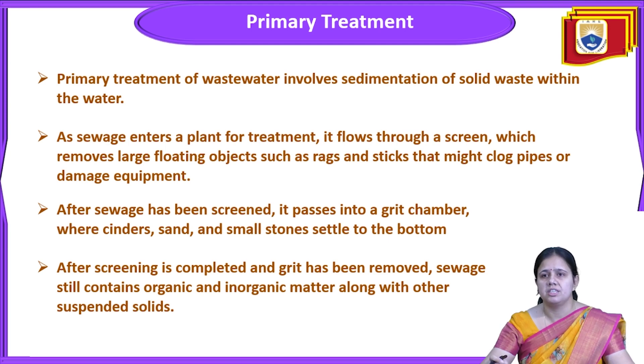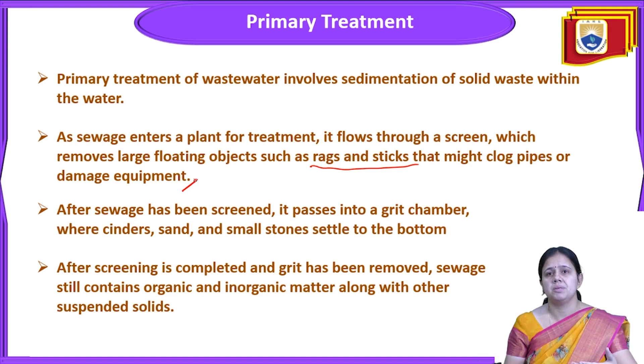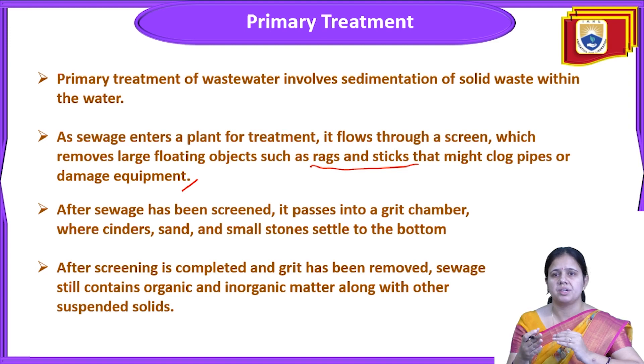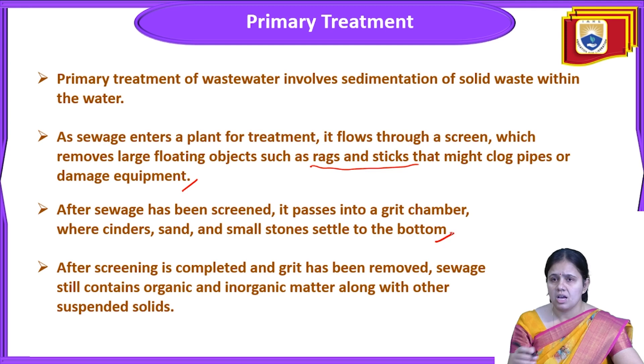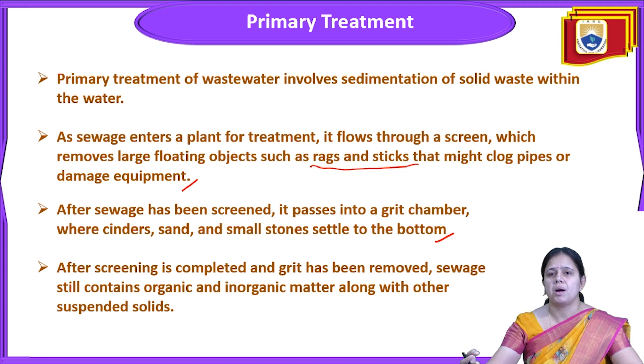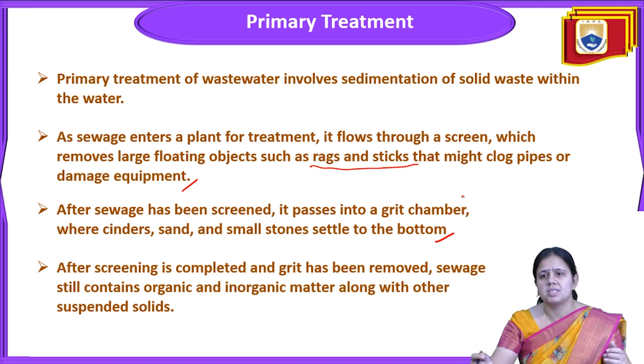As sewage enters the treatment plant, it flows through a screen which removes larger floating objects like rags and sticks that might clog pipes or damage equipment. After screening, the water enters the grit chamber where cinders, sand, and small stones settle to the bottom. After screening is completed and grit has been removed, the sewage still contains some organic and inorganic matter along with other suspended solids.